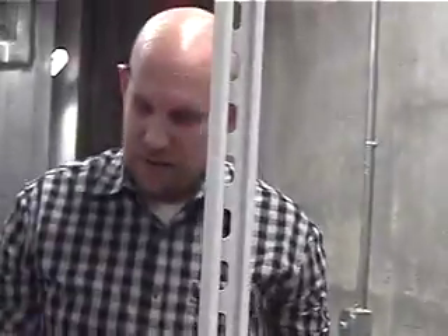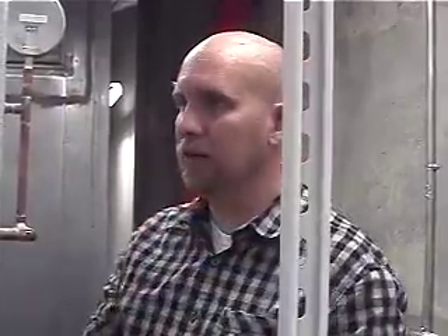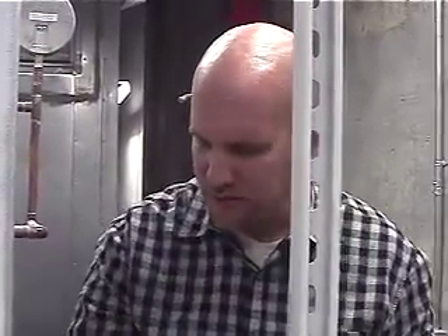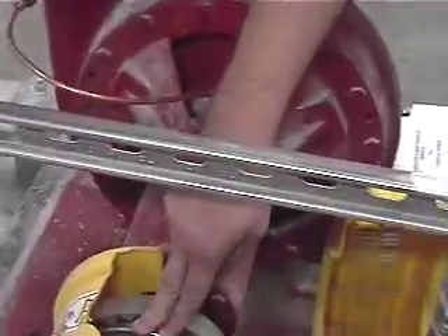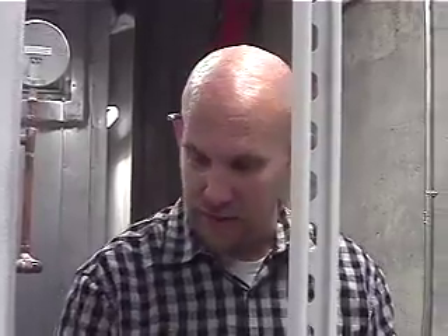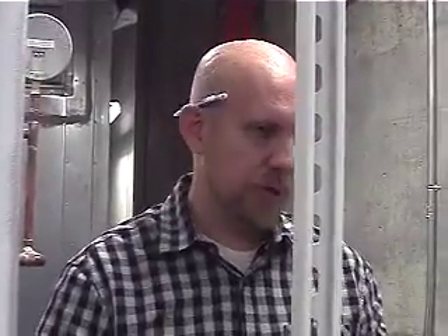Now this type here, it looks like these are on VFDs - do you know if they are? No, they're not, those two go to the chilled water. This coupler here is a little upgraded coupler, it's a VFD coupler, so it's a good thing, it's rated for VFD. With the VFD, because it's ramping up and down a lot, it will wear a coupler more, so I know those ones should have that same coupler, but this one as well - it's just a better coupler.